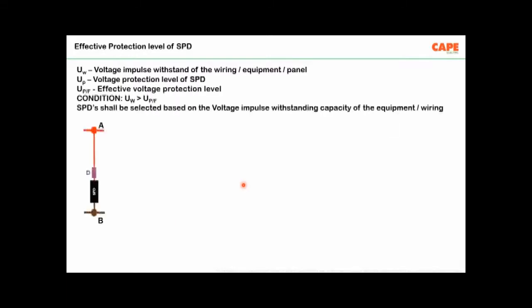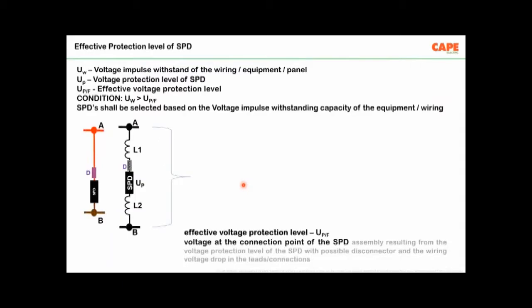The SPD, or surge protective device, is an important component in our electrical system. What it does is it reduces the radiated electromagnetic effect or radiated electromagnetic pulse. We have an SPD and we take wires and connect the SPD. We should understand that the effective voltage which is going into our system is the addition of the voltage drop in the wires, the protection level of the SPD and so on. What is recommended in the standard is to have very, very short wire. If possible, the wire length has to be 0.